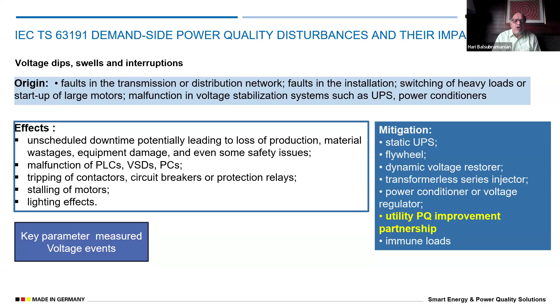But we need to understand it. Whoever is important, whoever is having it, should be in a position to correct it and then do it. The major, important aspect of what we need to collect as a voltage parameter is the voltage events. In EN 50160, it is classified by what level the voltage is going low and how long it is going low, and it is put in a matrix. So we understand this matrix and then try to understand how we do it.